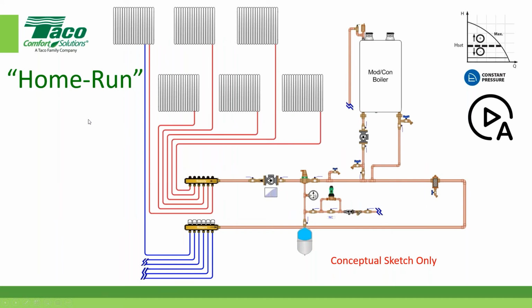Here's another look at a home run. This is more of a Siegenthaler kind of thing, where he's got the flexible PEX or PEX-aluminum-PEX going up to a panel rad. Notice that the panel rads don't have TRVs on them. They don't have thermostatic radiator valves. All the zoning's done back here at the manifold, in this case, a manifold in the mechanical room. So now I have corresponding supplies and returns. I'm going to go through and calculate which one of those is the worst, and that's what I would set that circulator at in a constant pressure application. And the same thing applies here as well.